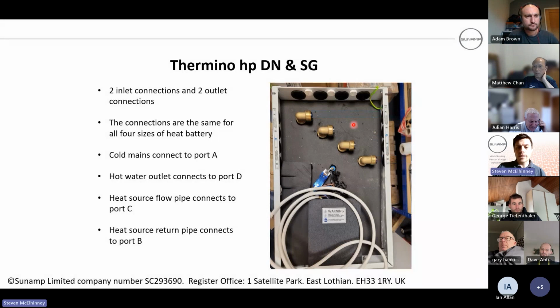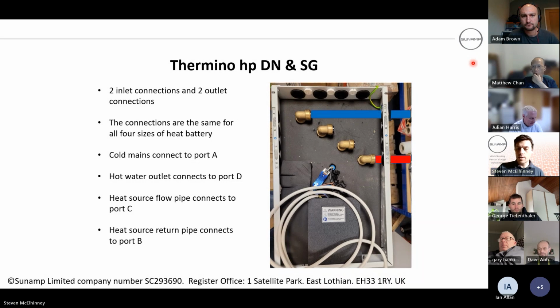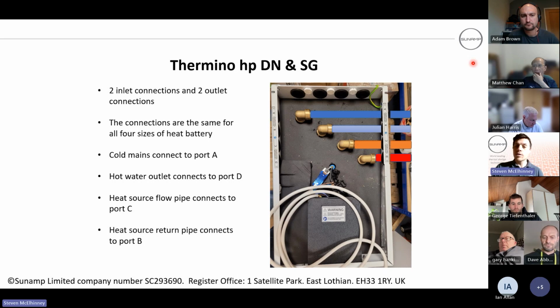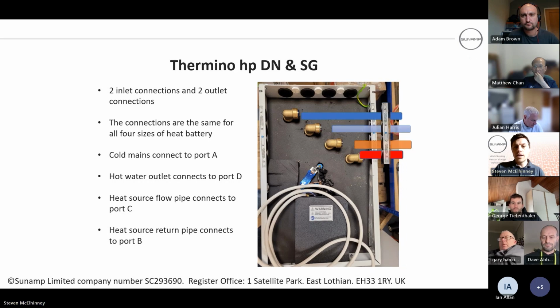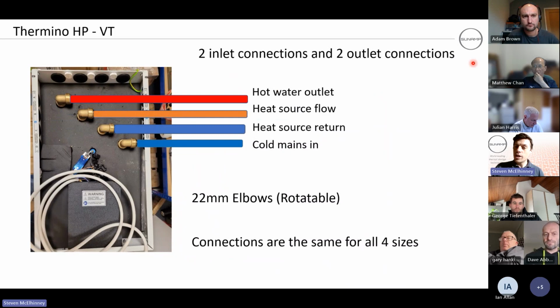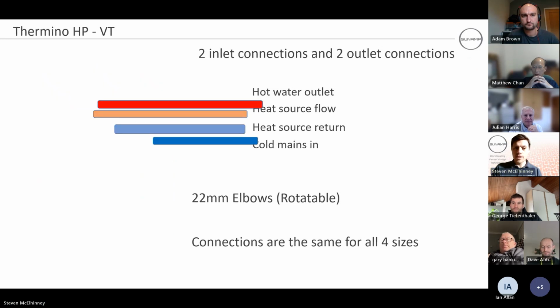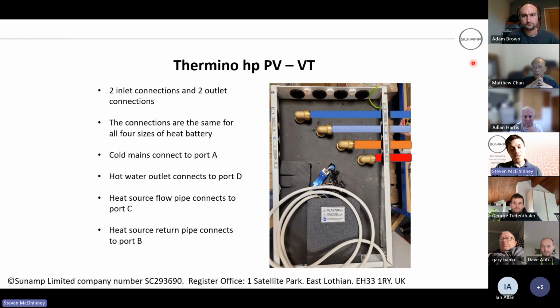So back to mechanical connections. The Daikin and Samsung models: cold water in, hot water out, then flow in, return out. So that's how it's always going to be for these models. When we change to a Vaillant, it changes again, opposite connections for those heat exchangers. Just remember that. But the Vaillant is compatible to work with PV, which is the Thermino HP PV-VT. So the pipework connections then change back again.